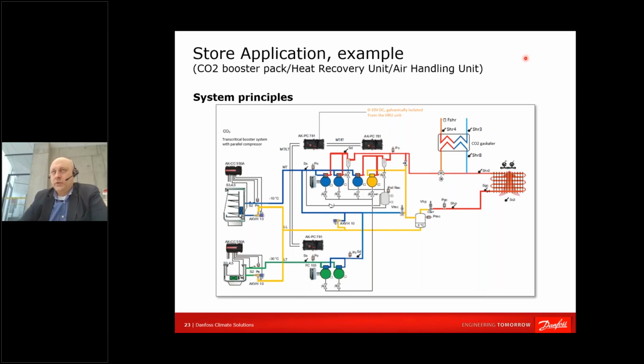And when we compared one of the systems for 300 kilowatts, we discovered that the pipes will be about DN80, or 80 millimeters in diameter. The complete system of pipes installation might be worth about 4,000 euros, just like that. So the customer is paying just 4,000 euros extra for the piping. Glycol, which should be poured in, would cost another 1,500 euros. So you see, it's not so easy to compare the systems.